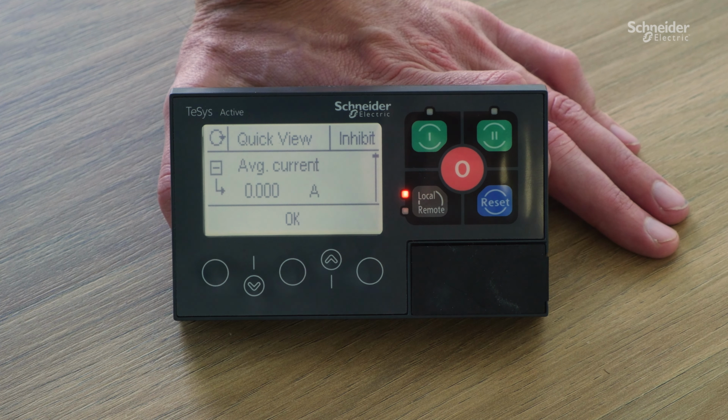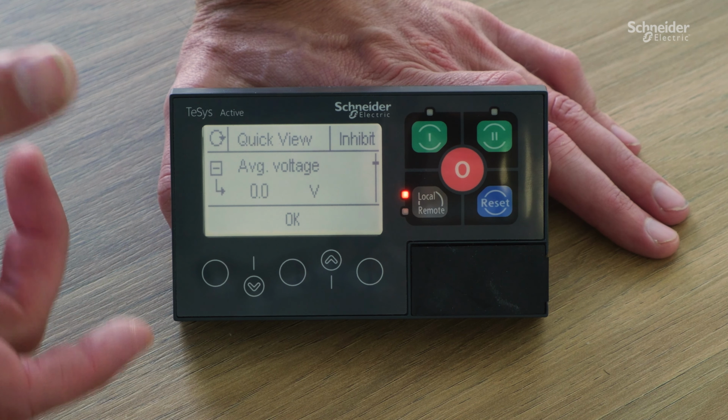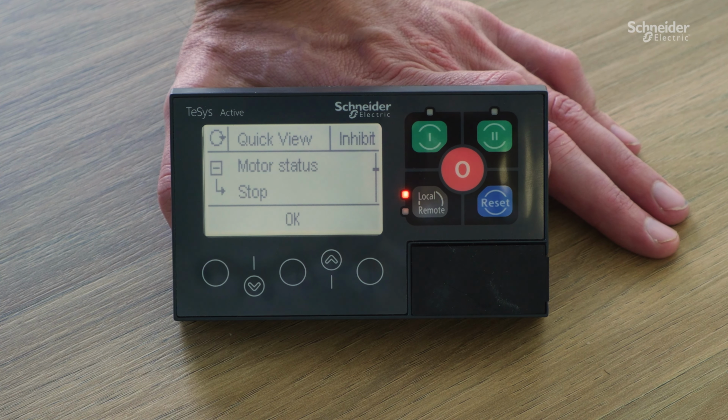We've now plugged the LTMTCUF module into the TeSys. Once it's started up, you may have an internal trip because the device itself has no configuration. From here, to set the IP address, we need to go into the menu. In my case, I have a blank pin, so I'll just use that. And we want to go all the way down to First Setup. In First Setup, we have some more menus, and in here, we're looking for Communication. Under Communication, we have Ethernet.